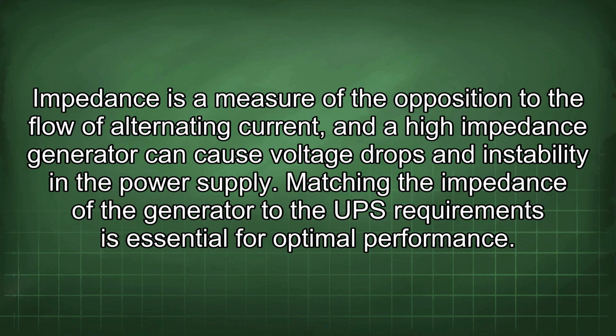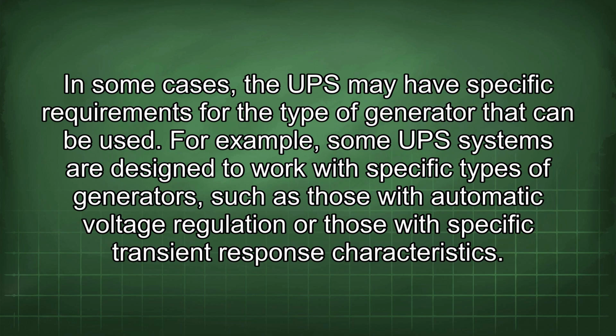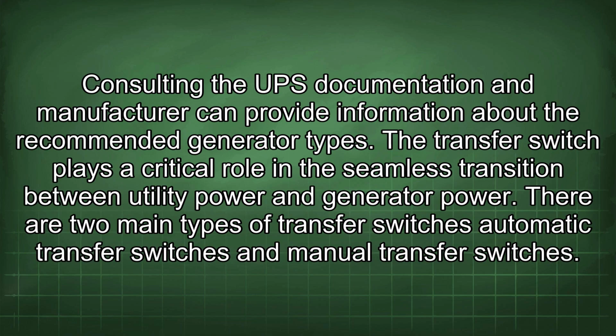Matching the impedance of the generator to the UPS requirements is essential for optimal performance. In some cases, the UPS may have specific requirements for the type of generator that can be used. For example, some UPS systems are designed to work with specific types of generators, such as those with automatic voltage regulation or those with specific transient response characteristics. Consulting the UPS documentation and manufacturer can provide information about the recommended generator types.